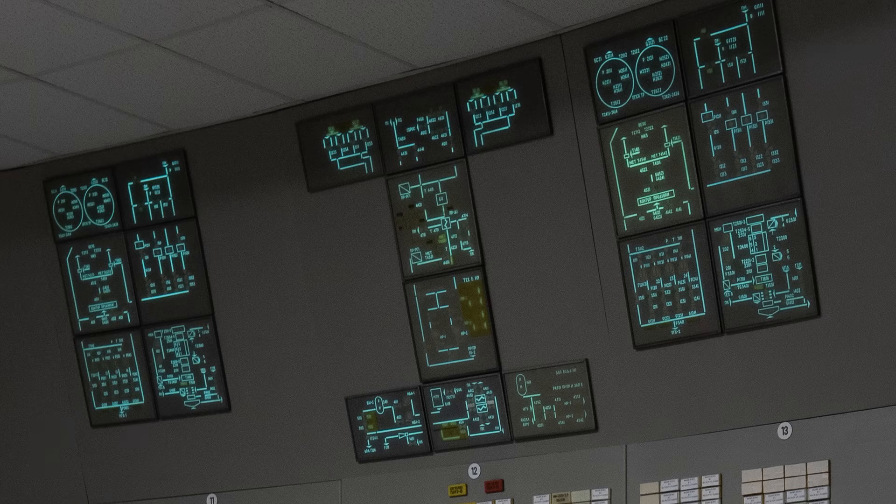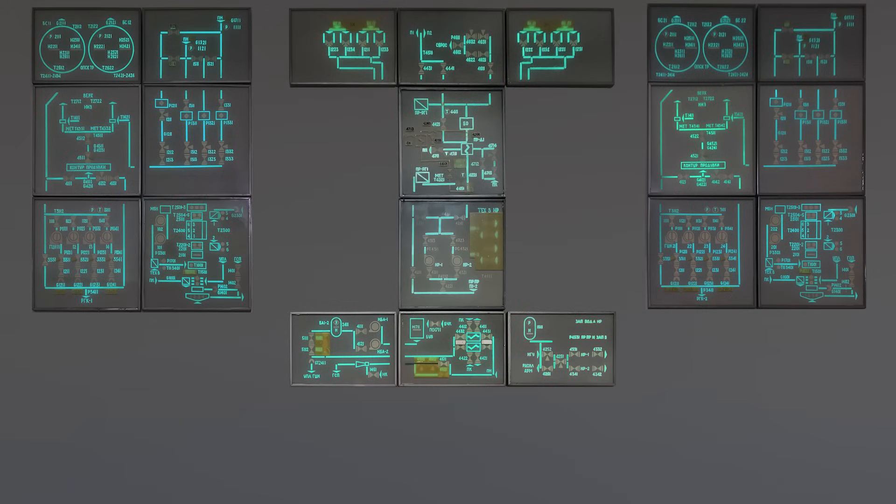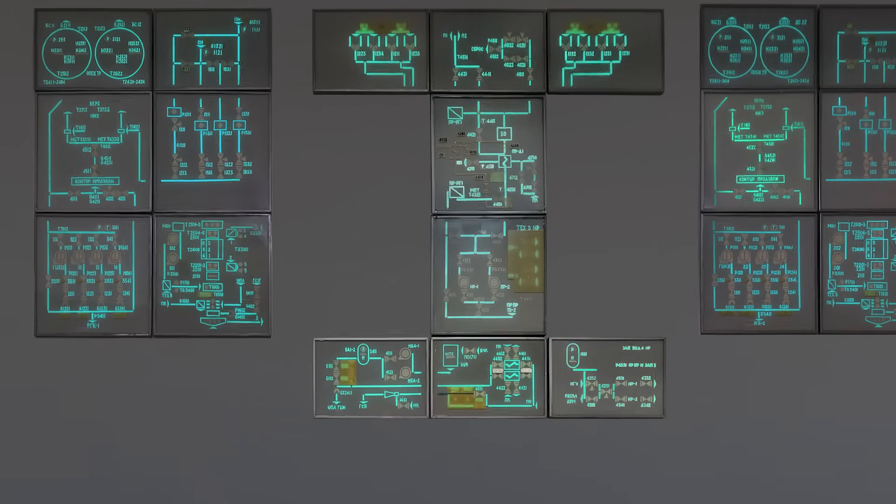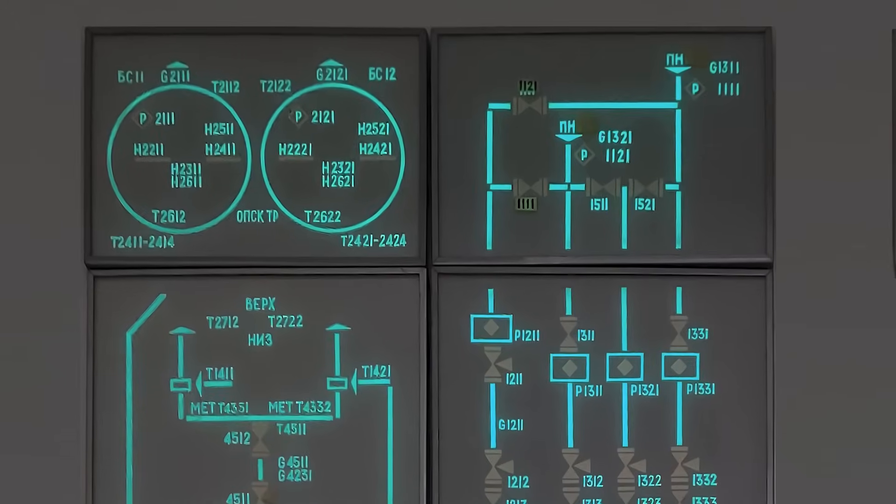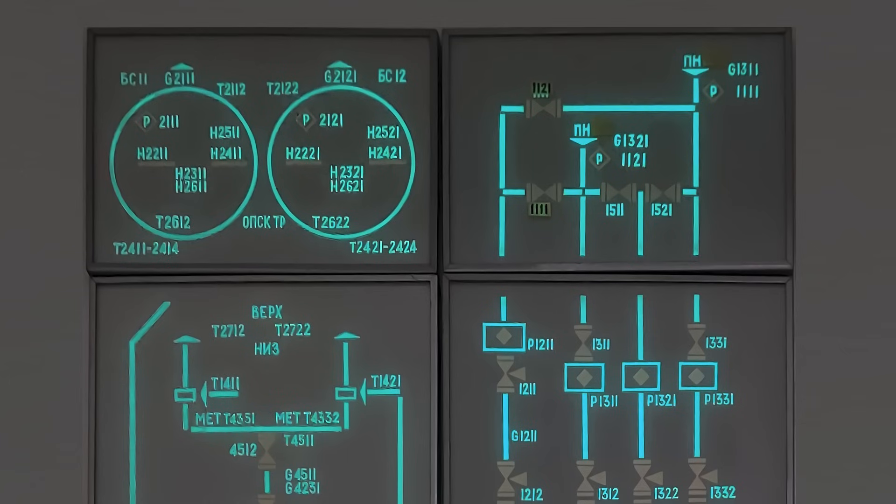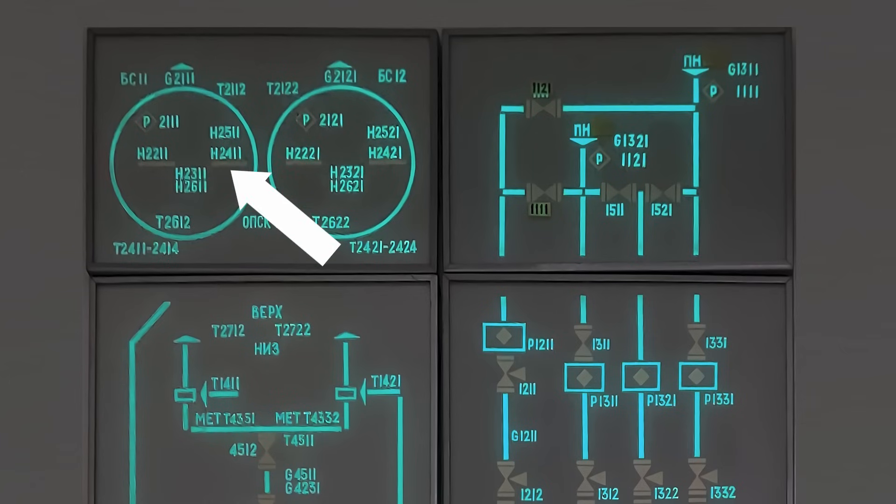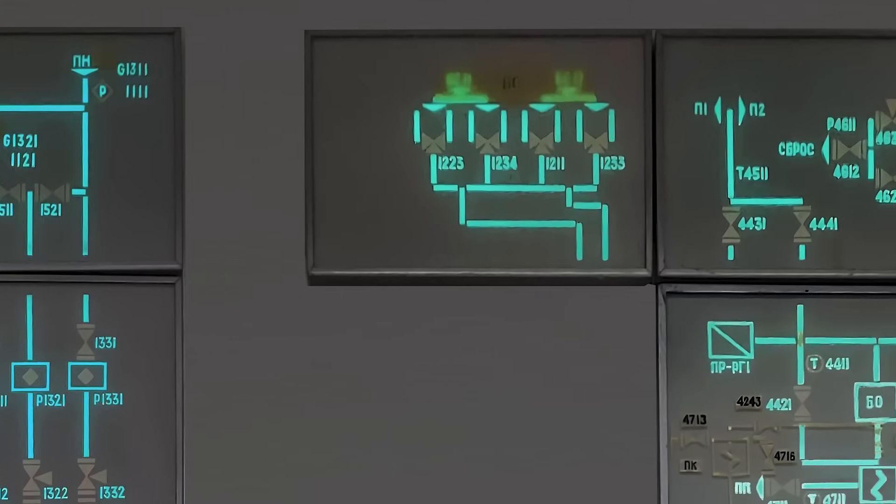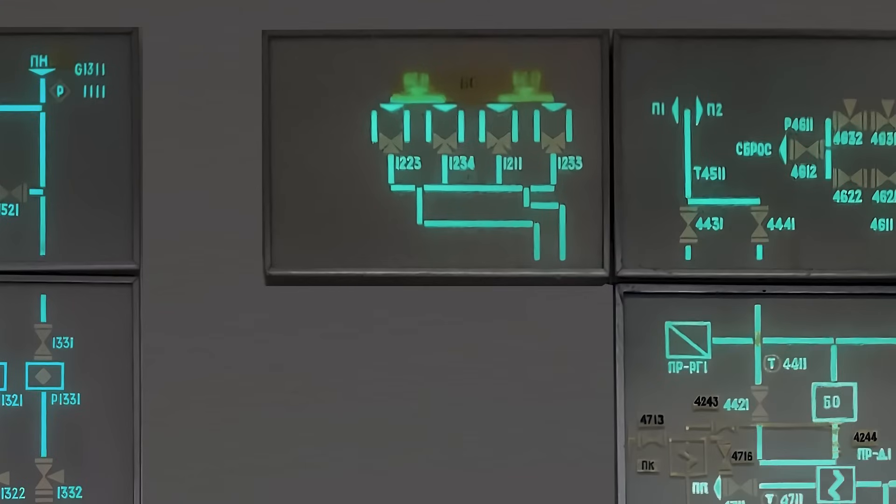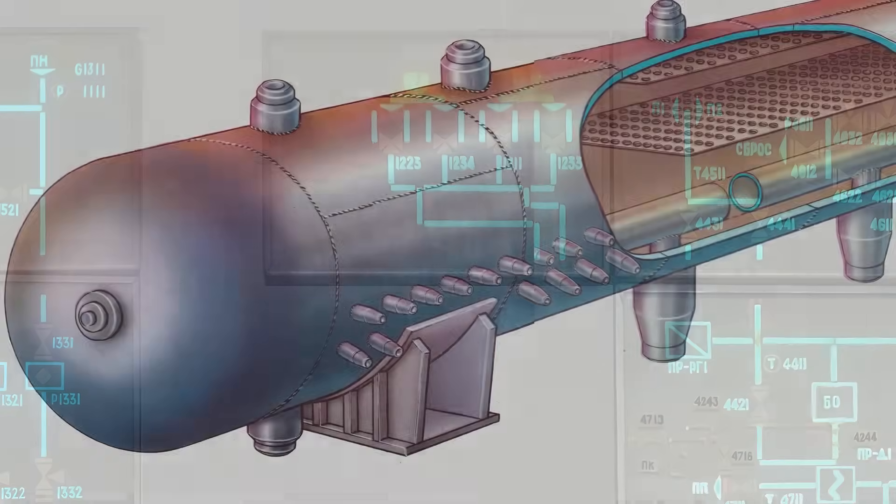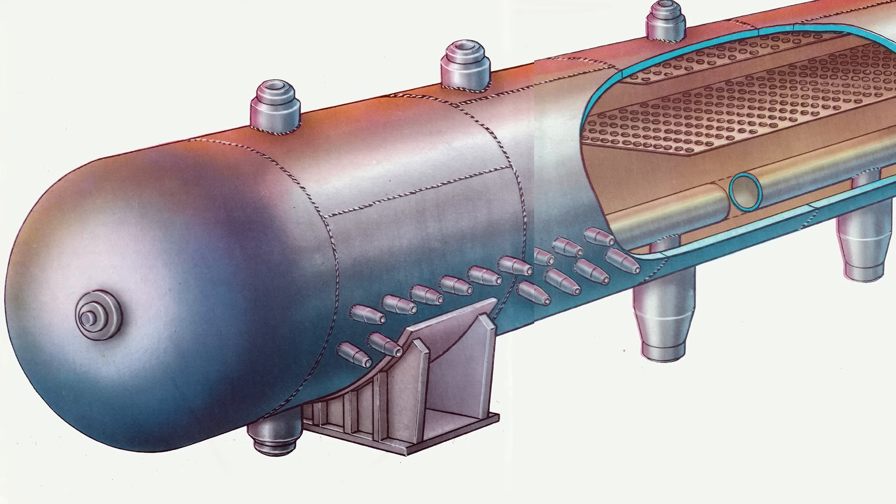And now let's move to something more interesting. So let's look at this large display. You already probably noticed it's mirrored, because left and right looks the same. That's because it shows the two sides of the unit which are symmetrical. Here these upper panels show warnings for pressure, temperature and water levels for the two drum separators. If pressure gets too high, here we'll see how a protection system triggers high-performance relief valves.